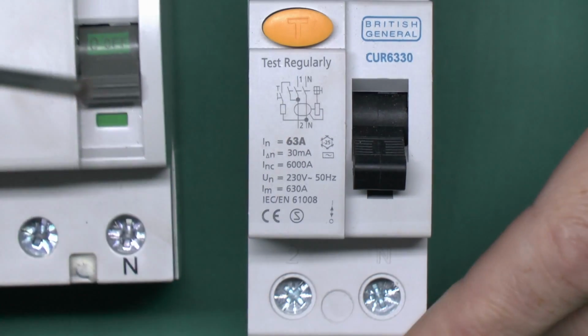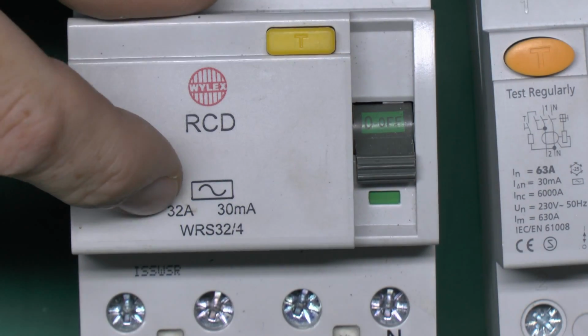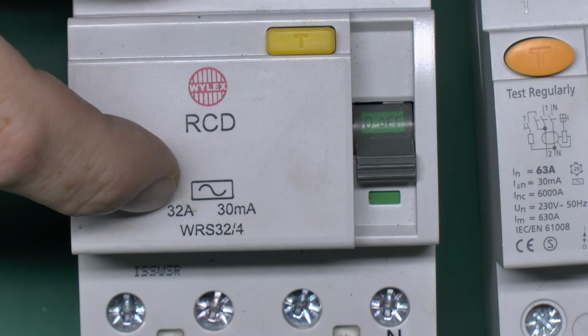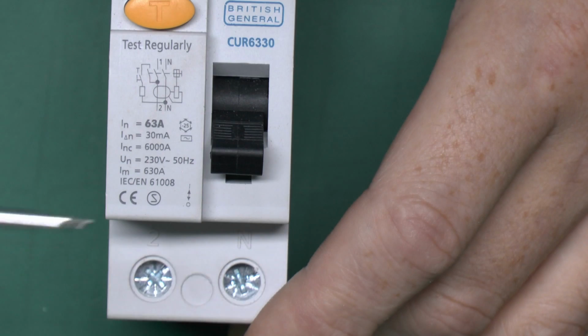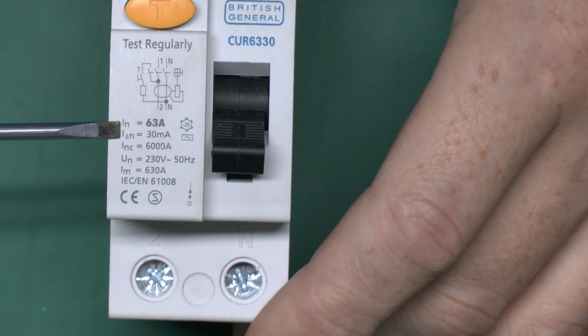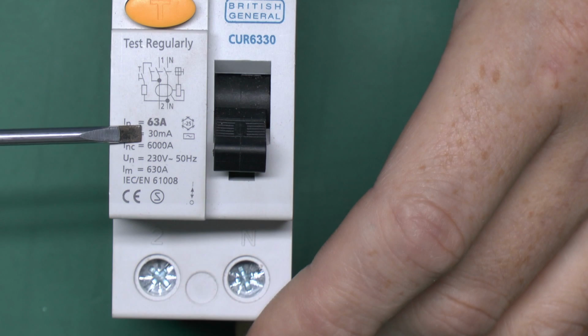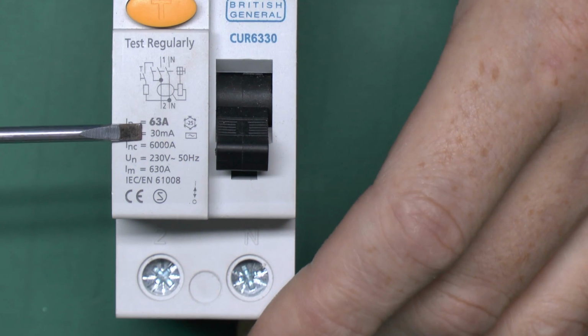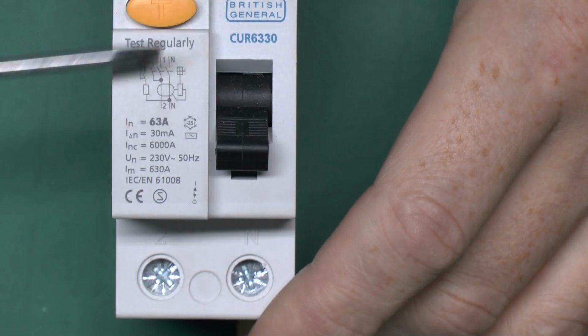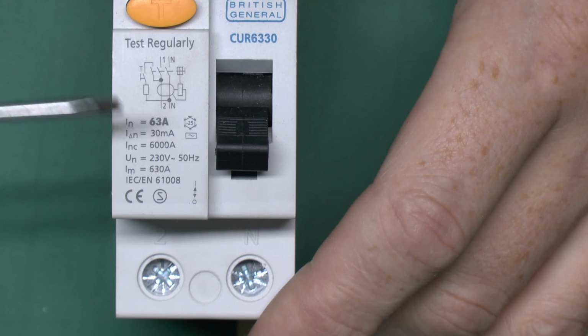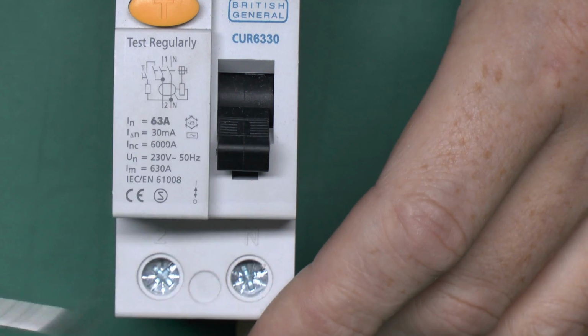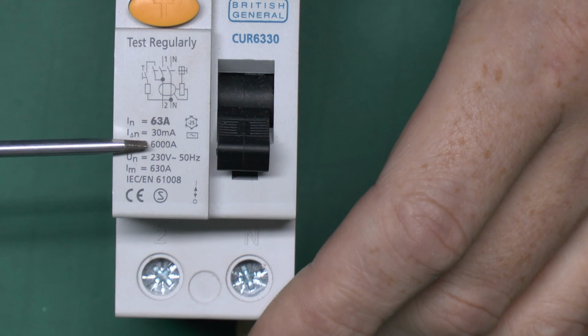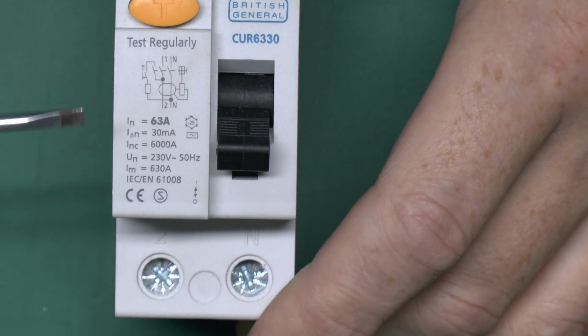In this particular case, the three-phase one, it's actually only rated to 32 amps maximum. But again, it's not going to trip on 32 amps because it's simply not designed for that. The information of interest on these is the rating here, which in this case is 30 milliamps. And this is the amount of imbalance that needs to occur for the device to trip. So in this case, 30 milliamps or 0.03 amps. And the other information is primarily the breaking capacity of the device, which we'll cover in another video, the voltage of course and the frequency, and obviously the various standards to which the thing is manufactured.